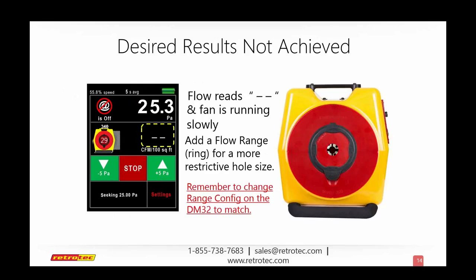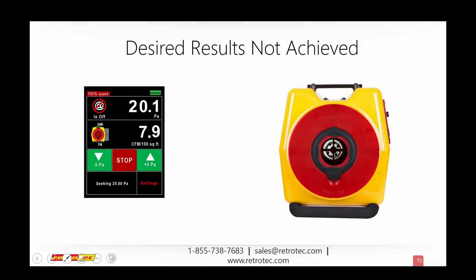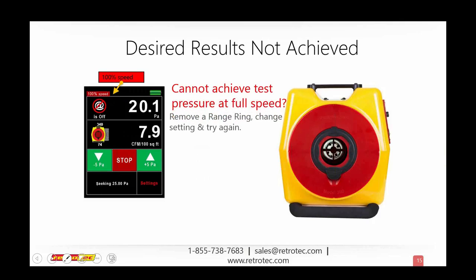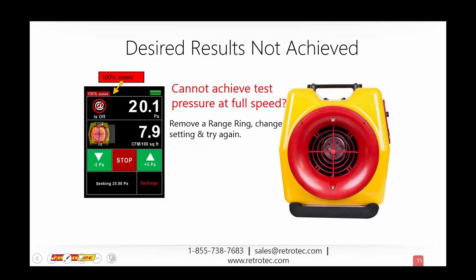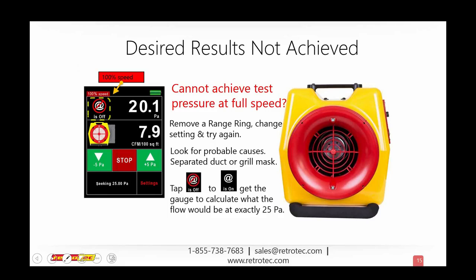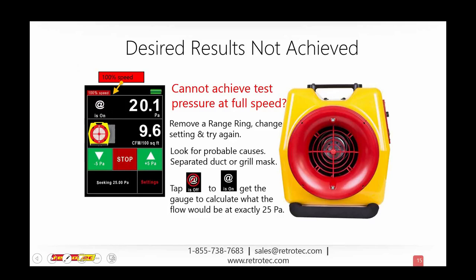So what if sort of the opposite happens? What if we get flow, but we cannot achieve pressure? Again, here I'm at full speed. My fan is, as we say in the music industry, completely dimed out. It's all the way up to 11, right? But I'm getting a flow, and I cannot achieve the pressure. So we can try the opposite. We can take off one of the restrictive plates, one of the rings or ranges or plugs, depending on your fan, so that you can get a larger volume of air moving through there. That ring, the configuration that you had with the plug, is actually impeding the volume of air through that fan. So you just take that off.